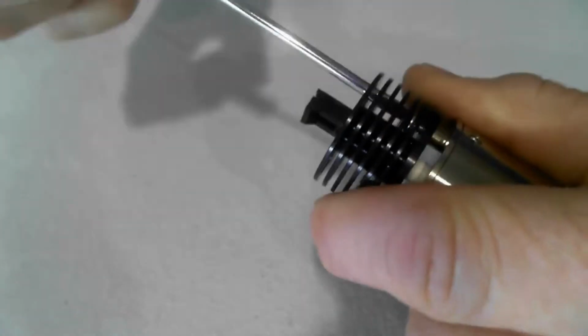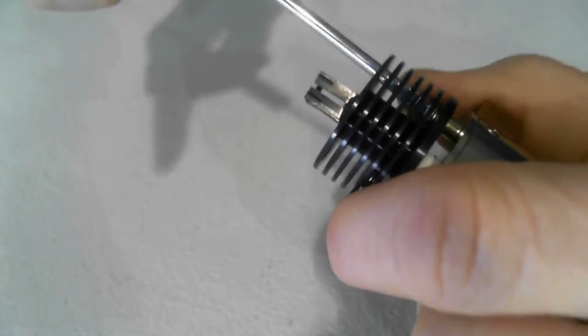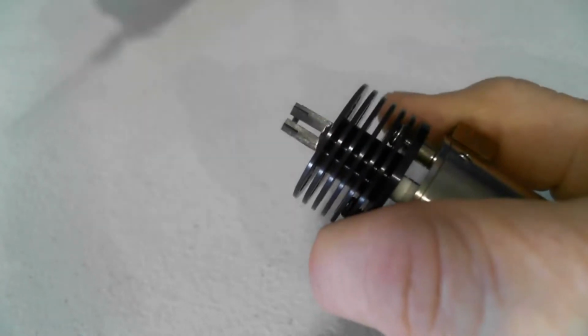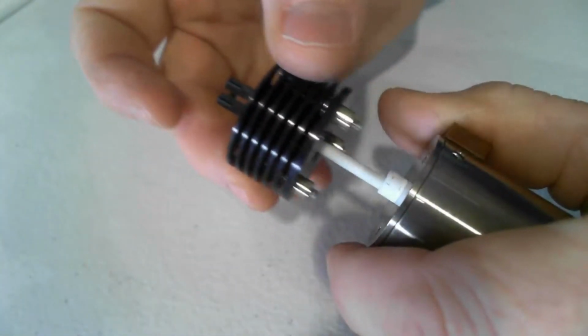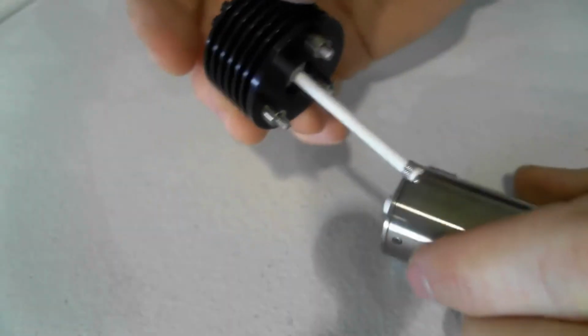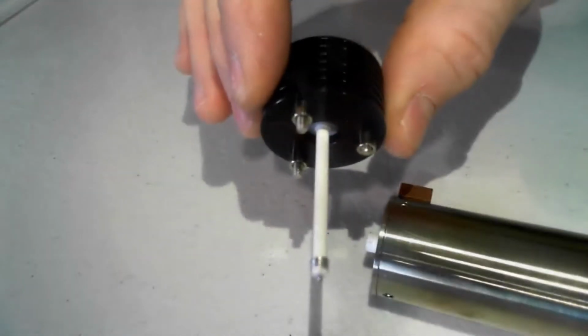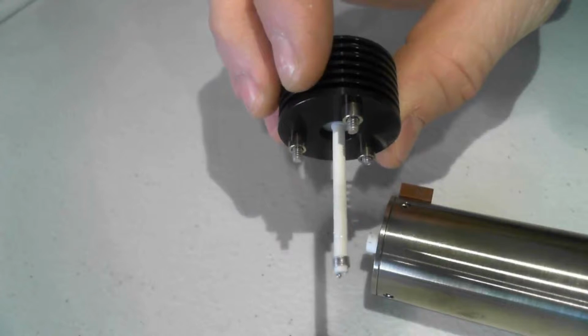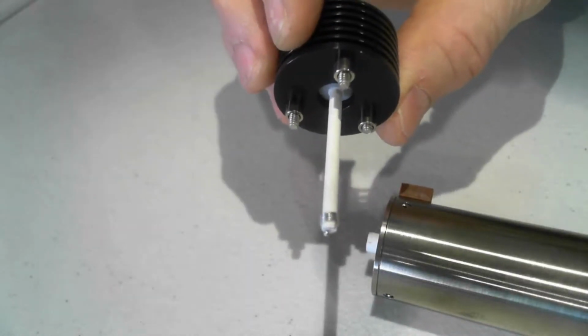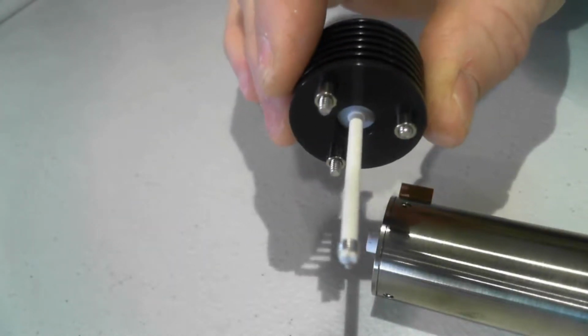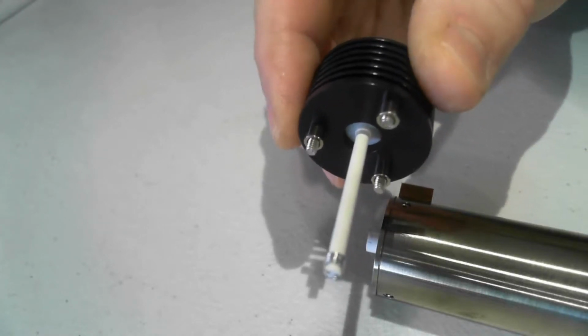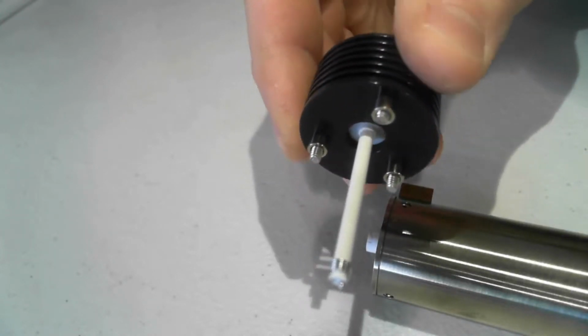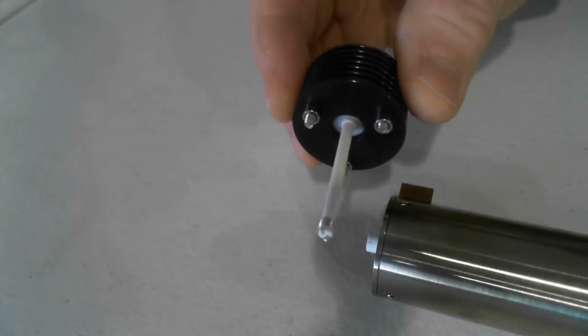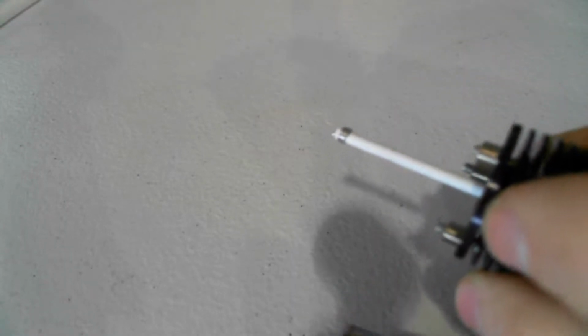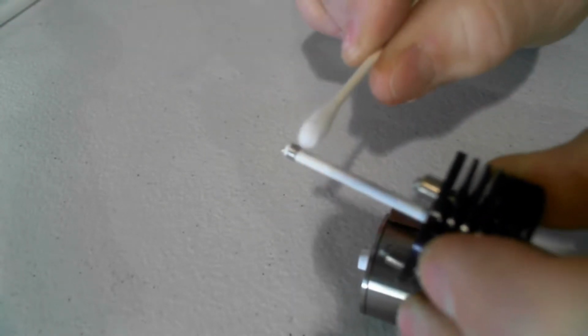Once the probe assembly has been removed, see if you can observe any shiny flakes or sparkles on the ceramic arm of the probe assembly. These flakes are bits of platinum that have split off of the electrode and collected on the ceramic of the probe assembly and also on the inner wall of the reactor core. These flakes reduce the XSD sensitivity by providing alternative locations away from the current measured electrode for free halogen atoms to bond. So we will want to remove as many of these platinum specks as we can.